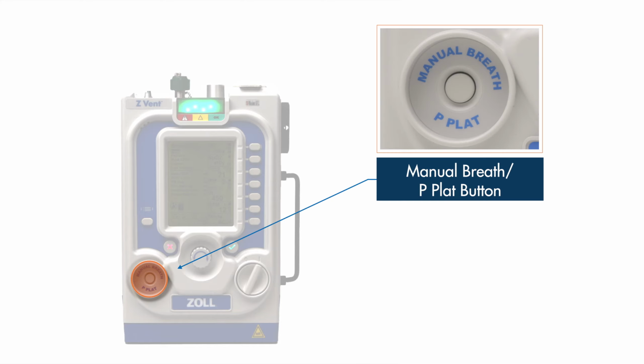In the lower left corner is the Manual Breath button. This button enables the user to deliver a single manual breath to the patient. If the ventilator supports the plateau pressure option, this button will also be labeled P-Plat. The user may press and hold this button to perform a plateau pressure maneuver.